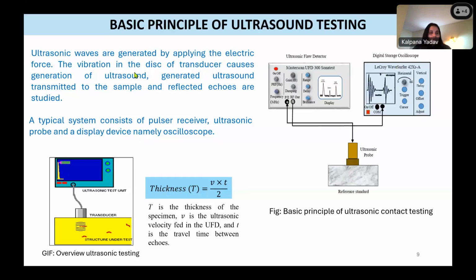So if we want to measure the ultrasonic velocity in the sample, you can see the formula here. Thickness equals velocity times time divided by 2. This 2 comes from the fact that the same transducer transmits the signal inside the sample and the same transducer receives those signals, so the transducer covers that path twice. That's why it's 2.